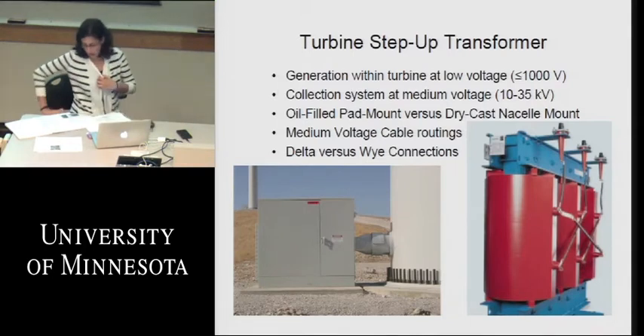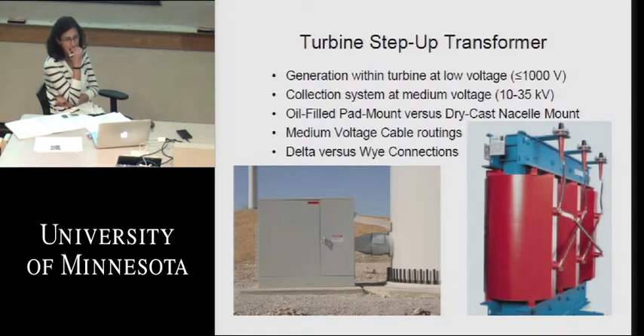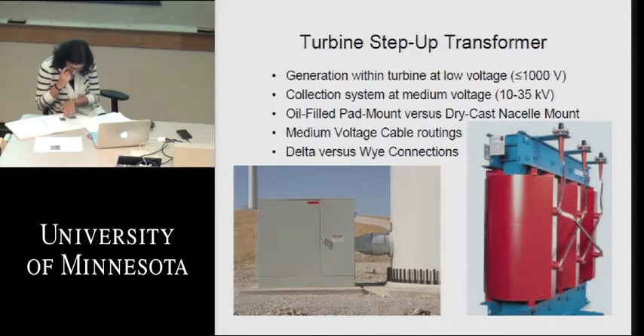Okay, so now looking at the transformers. Like I said, we showed two pictures here: one of the dry cast transformer on the right, and an oil bath transformer on the left. Again, this is a design choice that we as manufacturers make. The use of the dry cast transformers means that you can get away with very small cables coming out of the nacelle down the tower, and you can use very flexible cable arrangements because all three phases and the grounding conductor can fit into one cable.